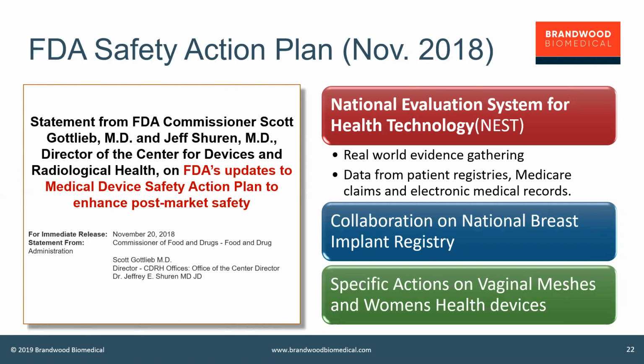I think one of the lessons of the big post-market databases, the MAUDE database especially, which has hundreds of thousands of reports going into it every year, is there's an awful lot of noise and not much signal in those databases. Yeah. And they're really hard to use, statistically useless, because it depends on the rates of reporting, which varies by device, by manufacturer, by device type. So MAUDE is good if you want to validate your assumptions in a risk assessment. If you assume there are certain failure modes, go and look at MAUDE and see if you're seeing those failure modes in other devices reported, but don't try and do statistics or whatever. And FDA have recognized that kind of post-market reporting is unfortunately of limited value.